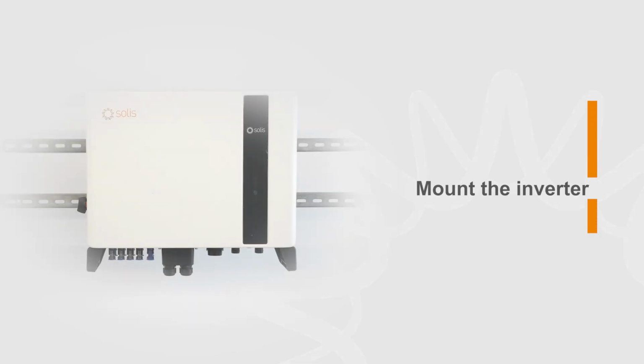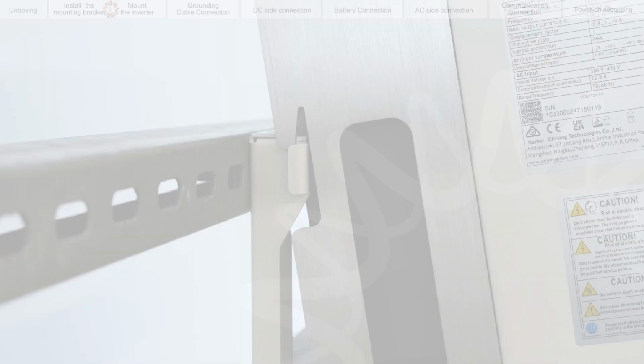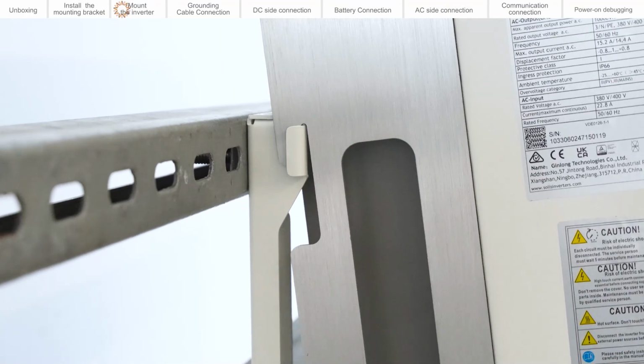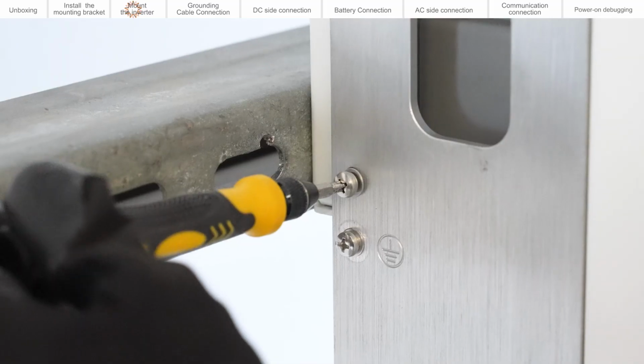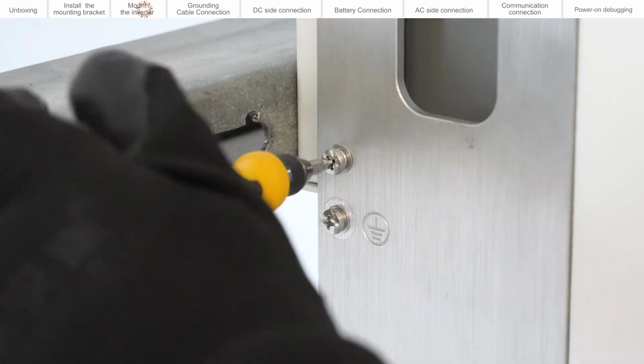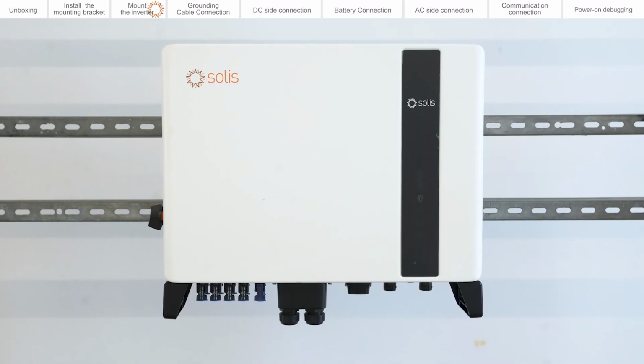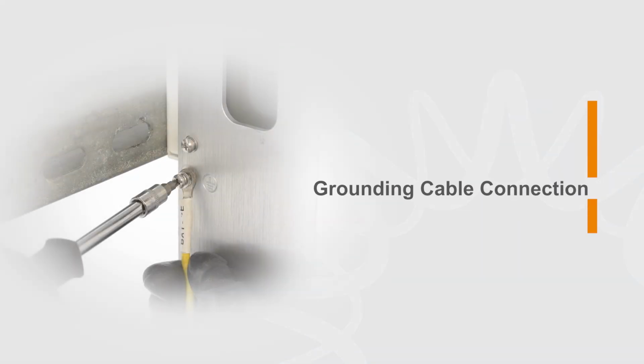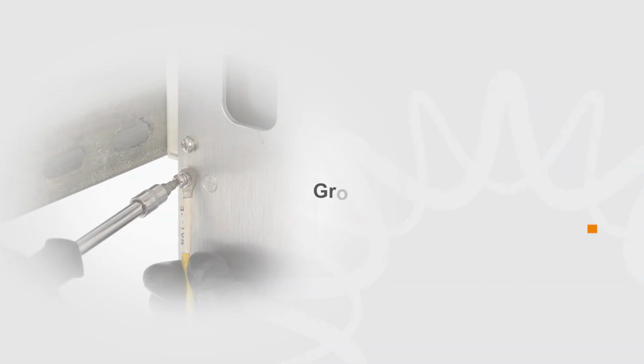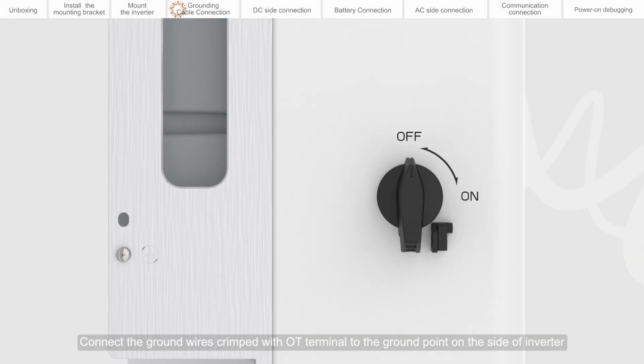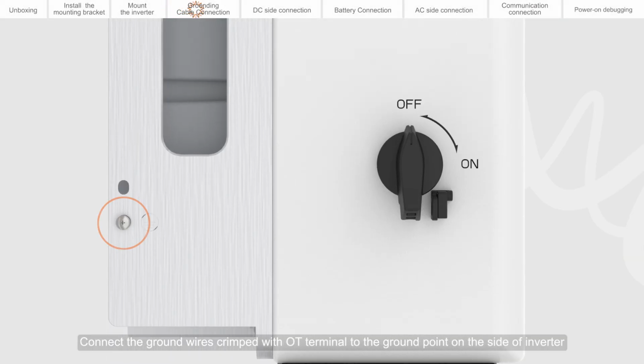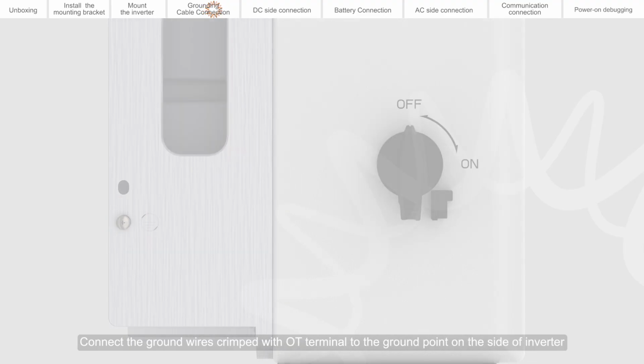Mount the inverter. Align the inverter with the hooks on the mounting plate and hang it. Screw the set screws into the fixing holes. Inverter installation completed. Grounding cable connection. Connect the ground wires crimped with OT terminal to the ground point on the side of inverter.